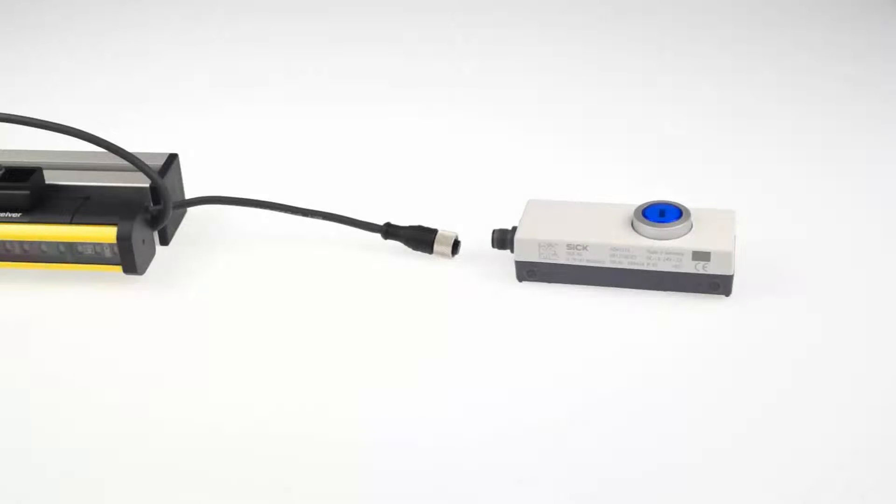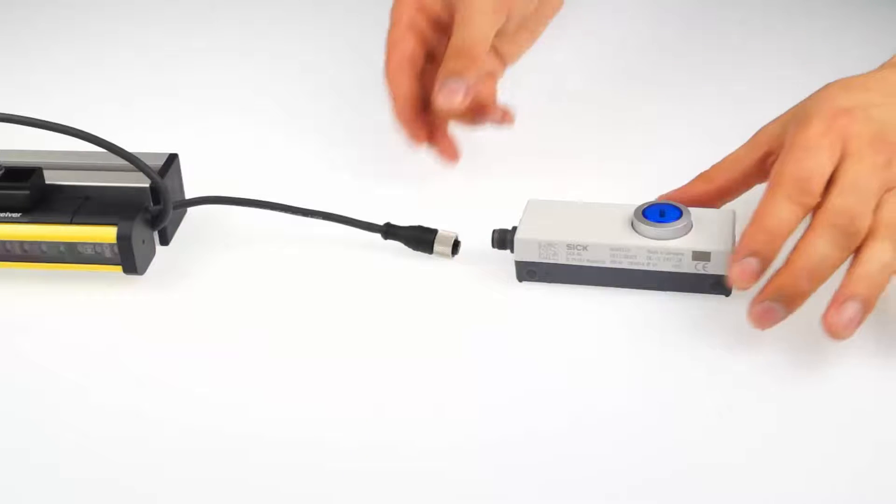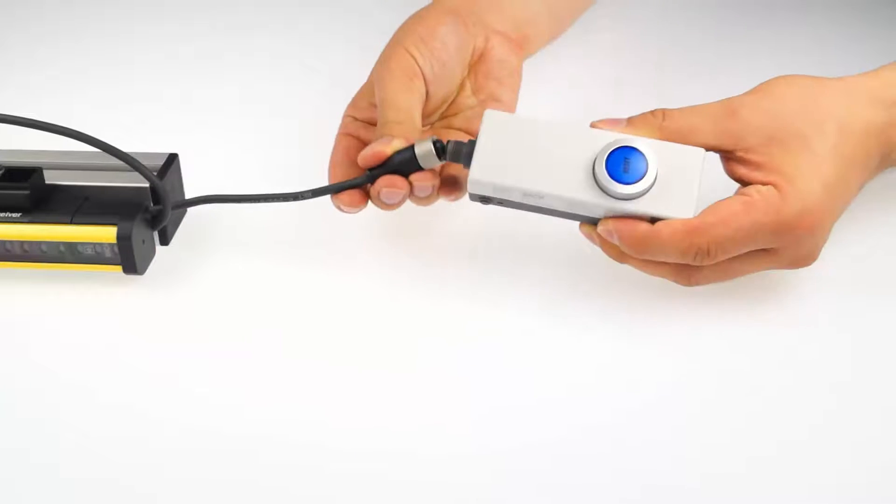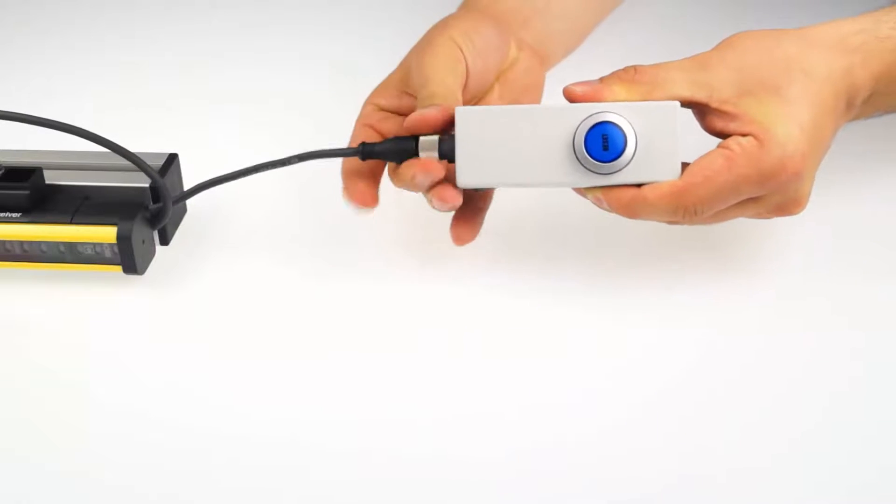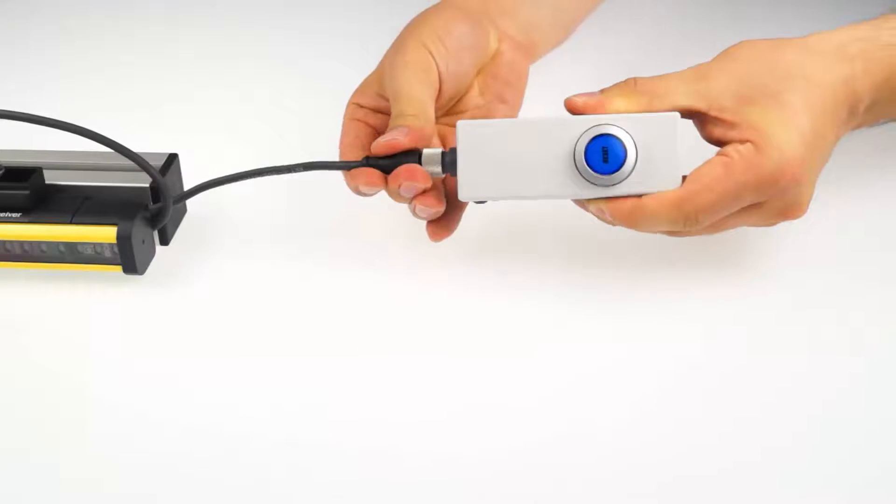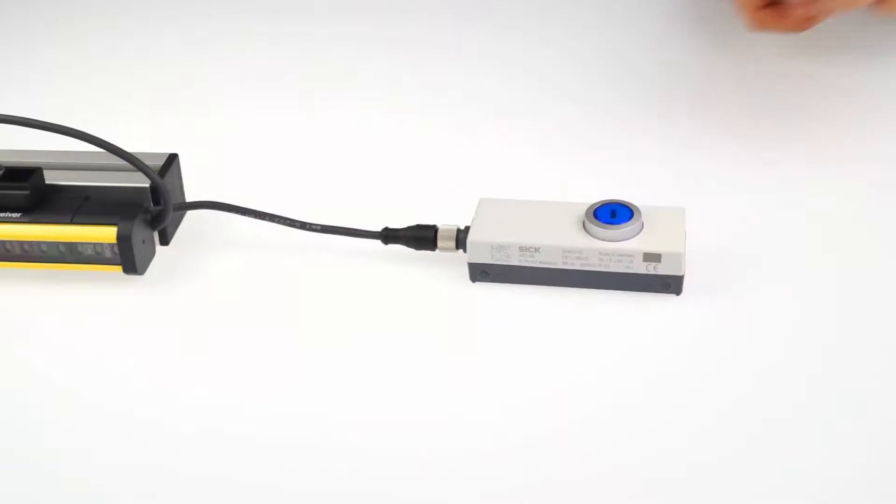If you now want to add a local restart interlock to the system, it is just as easy as the cascading. The reset button is connected to the last receiver in your cascade. Therefore, you also need a system plug with an extension connection here. While being disconnected from the power supply, connect the reset button to the open end of the extension connection on the receiver side at the end of the cascade.